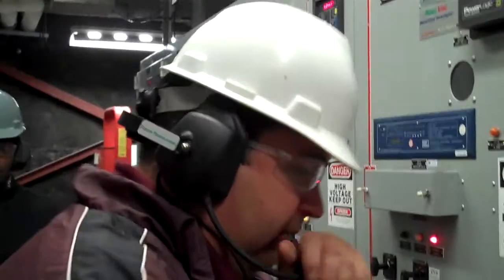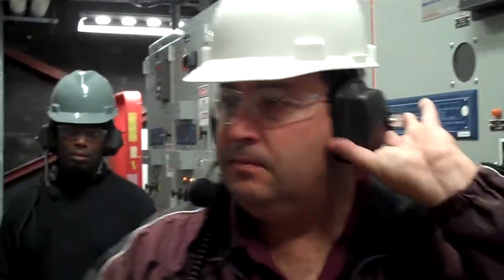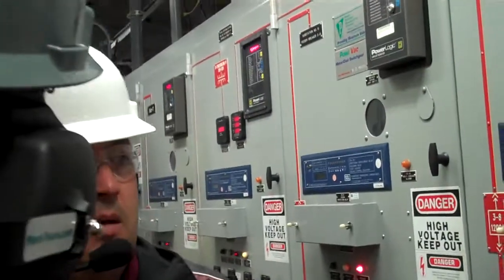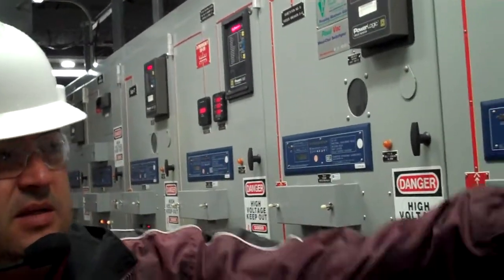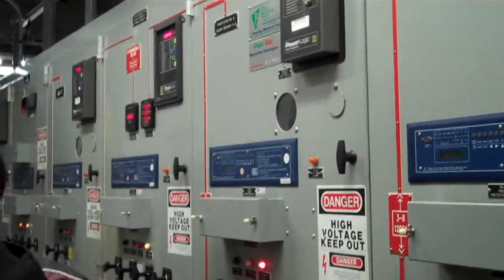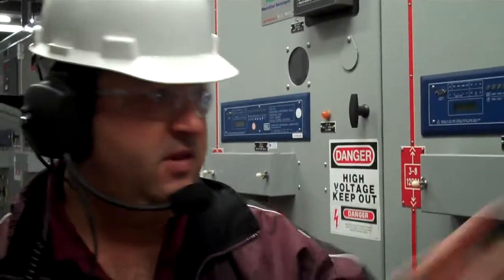I have a question. Go ahead. Do you have a backup relay? Because this looks like just a single relay. The protection, is it just a single protection? This is a single relay that has multiple functions. Yes. What if it goes out, if it faults? What happens? If this relay faults, we have inventory ones. We have the program where we can pop one in less than an hour.